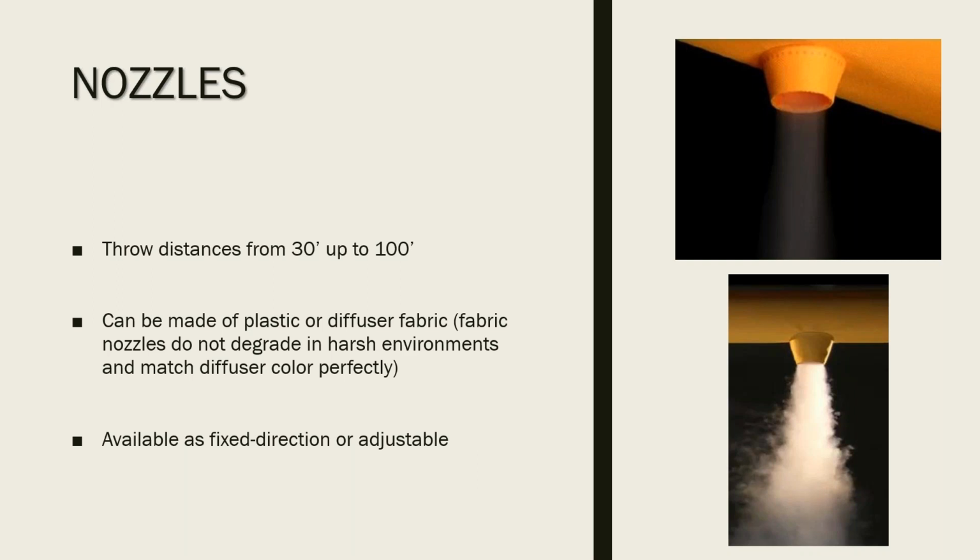You can use nozzles for throw anywhere from 30 feet up to 100 feet, and the size is based on how far you need to throw it. So these can come in as small as 3/4 of an inch diameter. They can go 3 inches and up, 6 inches.